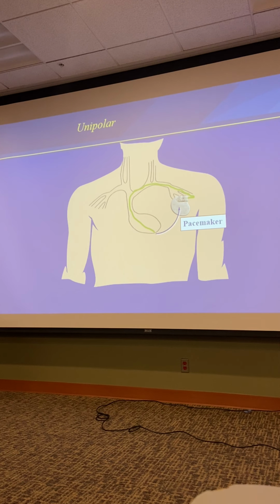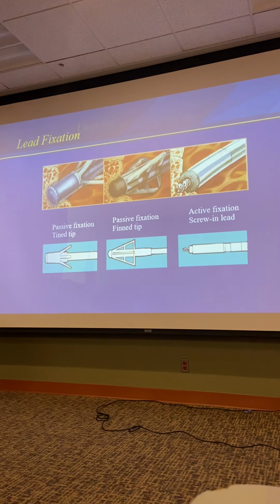When we put the leads in, let's see. What you can't see in this is the center of this lead is hollow. You can put a very long stylet, a very stiff wire, down the center of the lead, and that allows us to position it and move it very accurately and with precision. And at the end, once it's screwed into the tissue, we take that stylet out, and what's left behind is the lead is incredibly floppy and soft. So that usually prevents it from tethering the tricuspid valve open.